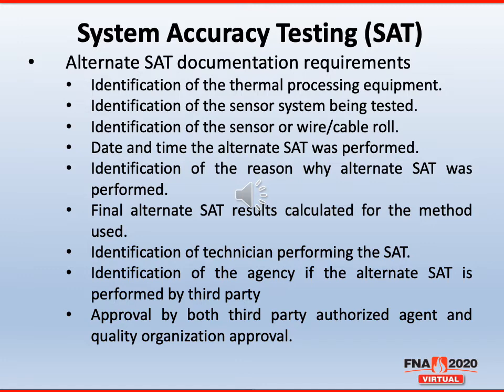You want to list the date and time the alternate SAT was performed, and identification of the reason why the alternate SAT was performed. So if you're just saying we have a single-use thermocouple, replace it, you could put in your documentation single-use sensor. Then the final alternate SAT results when you're doing calculations, and the method used. Identification of the technician performing the alternate SAT, identification of the agency if the alternate SAT is done by a third party, and approval both by the third-party authorized agent and the quality organization. So finally, we have some documentation requirements when it comes to the alternate SAT process.